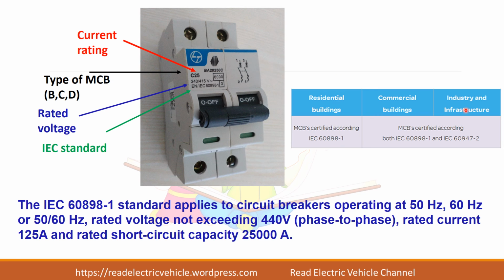If it is to be used in industry, it has to be certified by different standards. The difference is that in a residential building, the exposure of the MCB to pollution is less, whereas in industry it will be exposed to different chemicals, vibration and dust. So when the MCB is used for industrial purpose, it has to undergo a different set of tests so that it will be safe for the customers to use in industries.